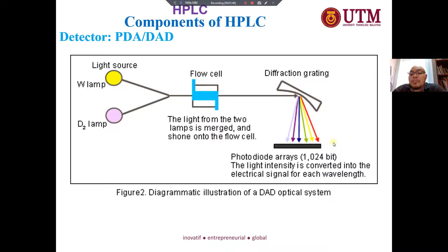It scans a range of UV rays to detect molecules with chromophores, usually in a range of 190 to 800 nanometers. It is capable of measuring multiple wavelengths at a time. It contains a holographic grating which spreads the compound light into individual wavelengths, and the photosensitive diodes can sense which wavelengths were absorbed. So at the end here, we have the photodiodes. Okay, multiple photodiodes, I can see.